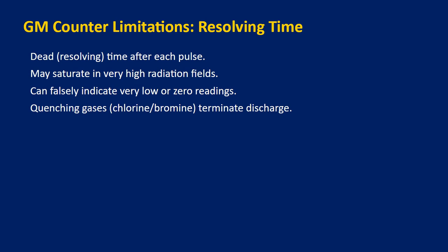For an RSO, this is a nightmare scenario. You could be standing in a lethal radiation field, but your GM meter is reading zero because it is paralyzed. Always approach a high dose area with an ionization chamber, not just a GM counter, to avoid this trap.